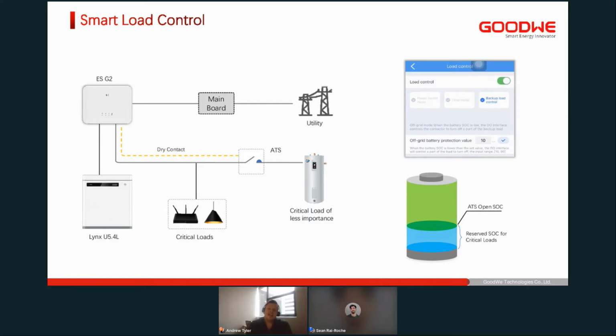And you'll see a visual representation of what we discussed earlier, which was having the ATS open on a specific SOC level for your battery. And then of course you've got a certain percentage reserved for critical loads, which in essence, if you reach that state of charge, that dry contact will send the signal to open that ATS so that it's no longer pulling power from the batteries.